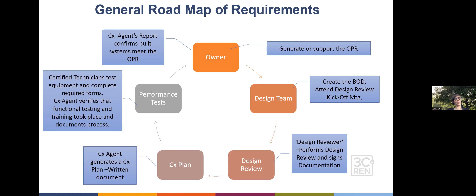The certified testing technicians perform the performance test, and the commissioning agent verifies those tests have been performed. All of that circles back to the owner to confirm the building performs to what the owner wanted in the first place. That's the commissioning report at the end, making sure all these pieces come together to get the performance metrics accounted for.